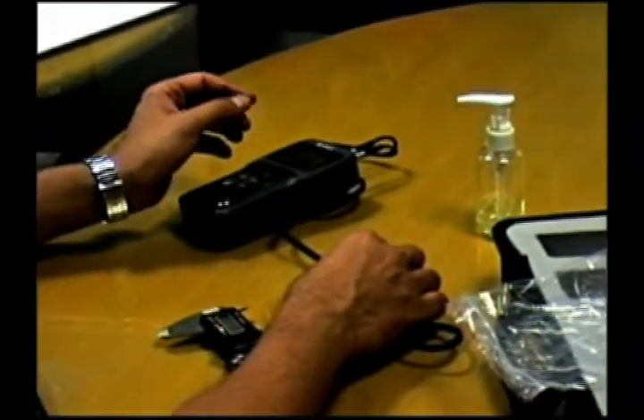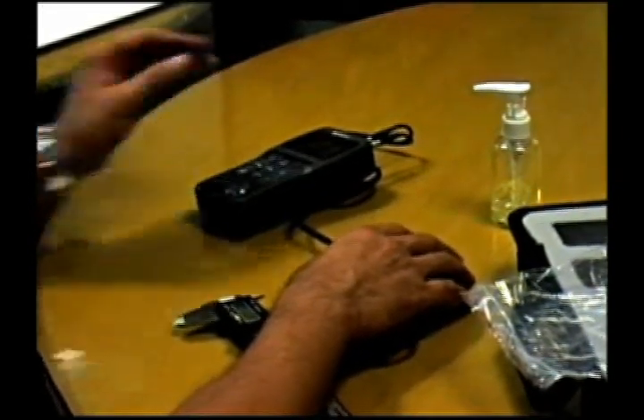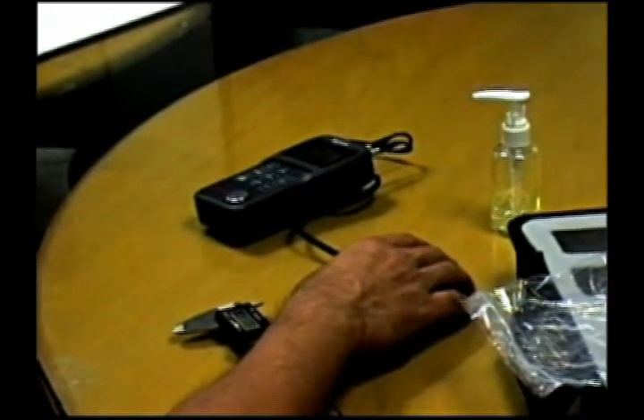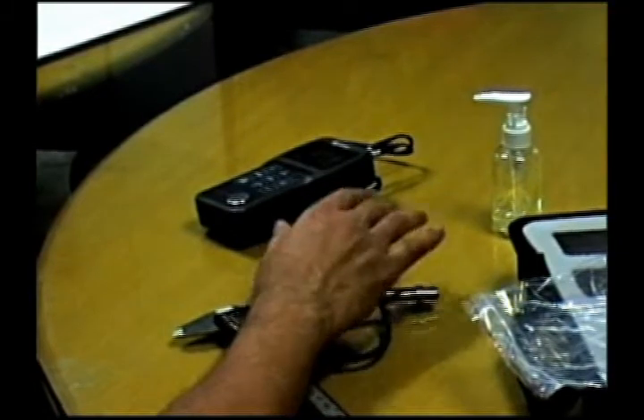What we are signifying is that before the instrument is utilized to test the thickness of any material for which a quality control test is going to be done, it is important to calibrate the instrument to that material.